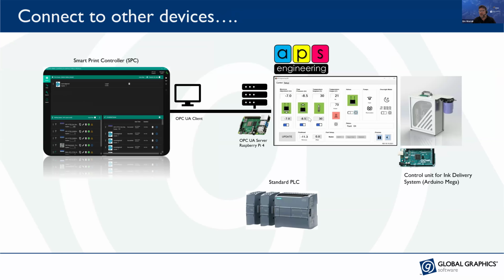We connect up to software and have different clients for front ends, but we also wanted to connect down into devices. In the early days, we worked with an ink delivery system that used a serial protocol with its own UI. We took that serial protocol and built a gateway using a Raspberry Pi with an OPC UA server in it. We collected the data using their protocol and exposed it via the OPC UA server to pull that data into our product. Then we had a panel in our product that let you work with their ink delivery system - start and stop it, get temperatures back, that kind of thing - using the OPC UA server built into a gateway for their product.